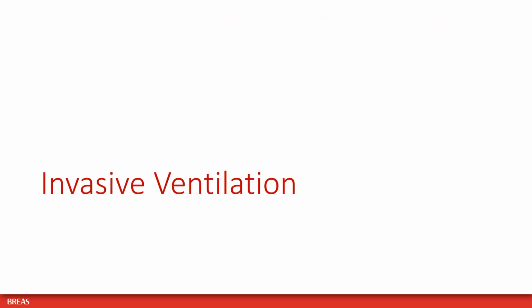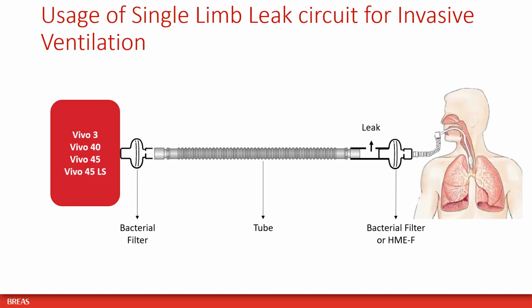Please follow these recommendations when using your Vivo ventilator for invasive ventilation. When using a single limb leak circuit for invasive ventilation, place a bacterial filter at the air outlet of the Vivo ventilator and a bacterial filter or HME with filter between the leak adapter and the patient.